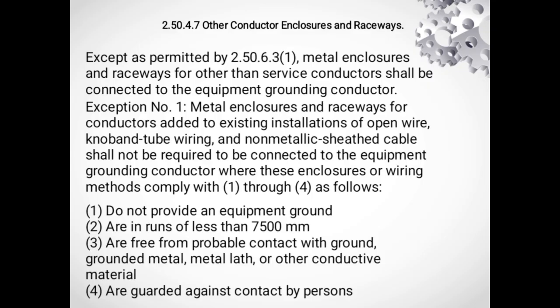2.50.4.7 Other conductor enclosure and raceway. Except as permitted by 2.50.6.3, 1. Metal enclosure and raceway for other than service conductor shall be connected to the equipment grounding conductor. Exception number 1. Metal enclosure and raceway for conductors added to existing installation of open wiring, knob and tube wiring, and non-metallic sheathed cable shall not be required to be connected to the equipment grounding conductor, where this enclosure or wiring method complies with 1 through 4 as follows. 1. Do not provide an equipment ground. 2. Are in runs of less than 7,500 mm. 3. Are free from probable contact with grounded metal, metal lath, or other conductive material. 4. Are guarded against contact by persons.